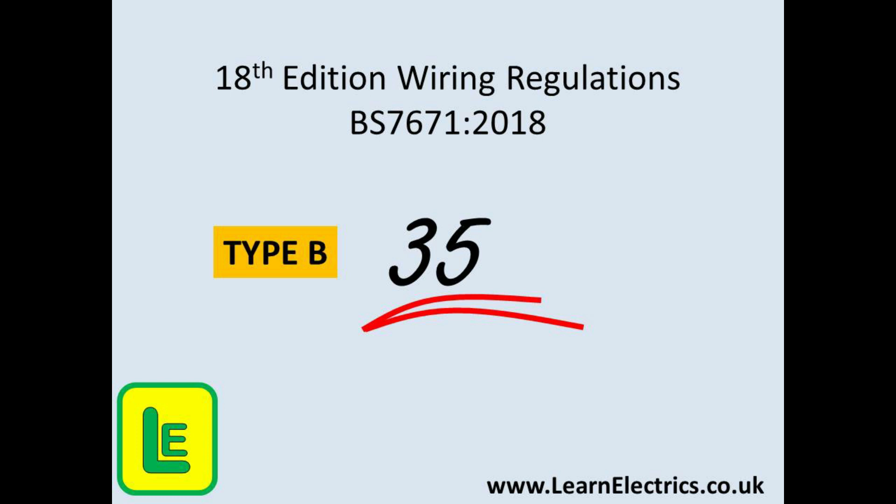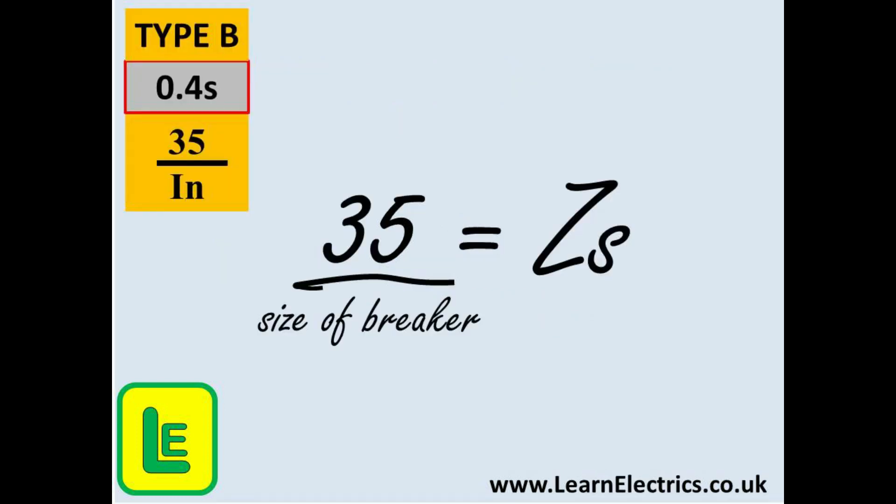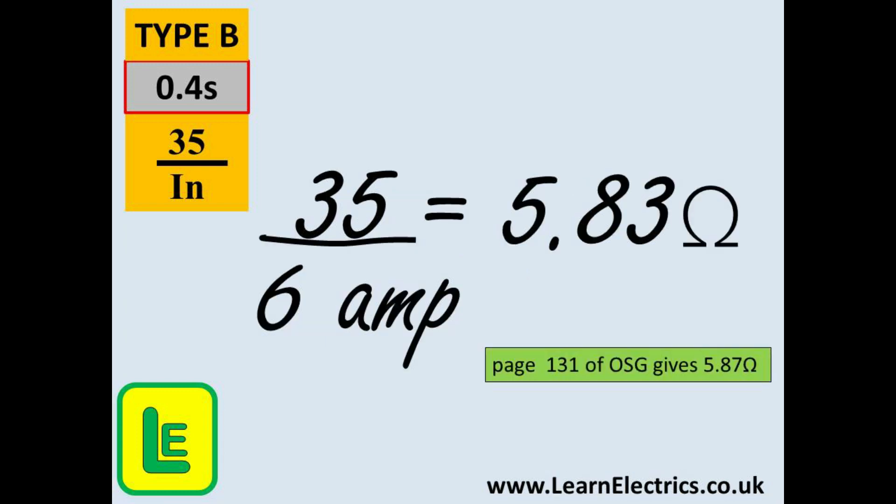First, we need the number 35. Then we divide the 35 by the size or rating of the circuit breaker and this will give us the maximum measured ZS value. At the top left of this slide I have repeated this information. We have a 0.4 second disconnection time. It is a type B breaker and so the calculation is as shown: 35 divided by IN where IN is the size or rating of the breaker.